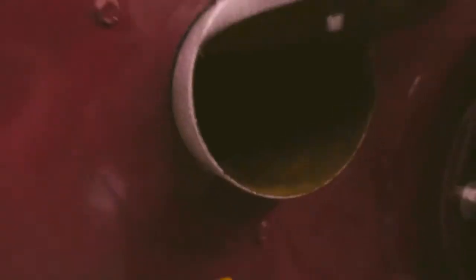We're going to shut the oil off for the flame here. See how the flame gets smaller and smaller and then the burner shuts off. That's because of not enough oil flow.